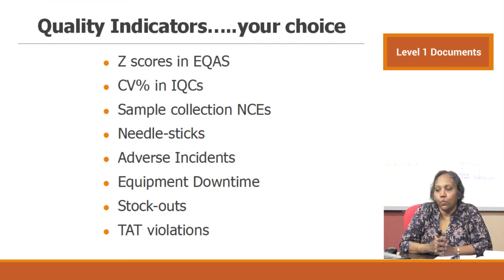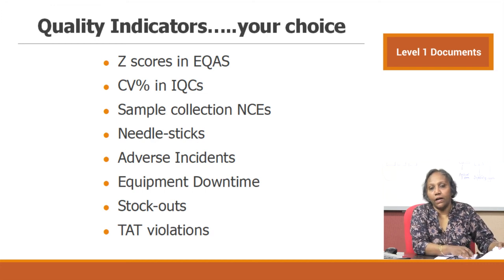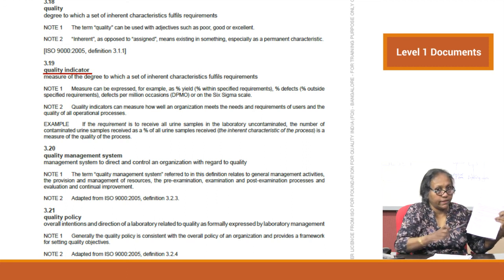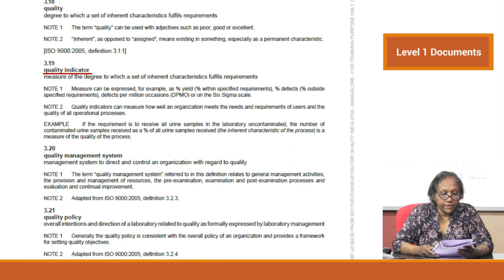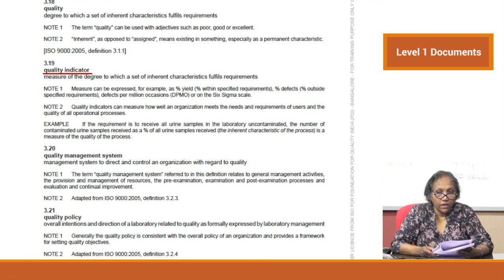NABL recommends that at least one indicator be set in pre-analytical, analytical, and post-analytical areas — but the more indicators you have, the easier monitoring becomes. Clause 3.19 of the standard defines quality indicator as a measure of the degree to which a set of inherent characteristics fulfill requirements. It can be expressed as percentage yield, percentage defects, percentage outside specified requirements, defects per million occasions (DPMO), or on the six sigma scale.